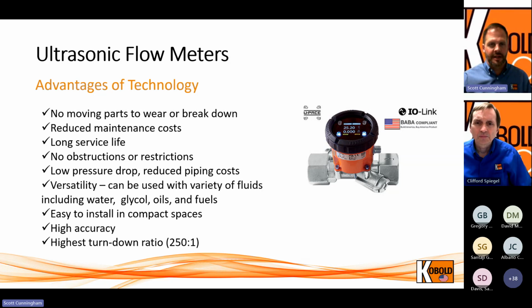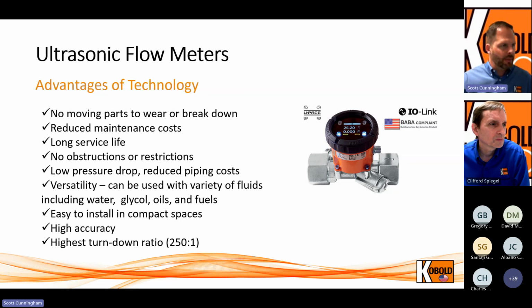There's nothing to wear out or break down. Obviously, that leads to no degradation, no maintenance costs associated with having to replace paddle wheels or replace flow meters because of wear and tear on the mechanics. We get extremely long service life, and because you don't have anything in the path, you don't have any pressure drop, which means you've got reduced piping costs, and you don't have to compensate for pressure drop with over pumping your motor, right, Cliff? Yeah.